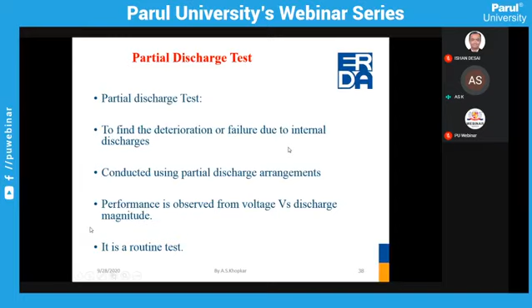So let's say we have produced 100 units. Out of that, we randomly select a sample, and then a few tests we conduct on those samples. If those samples pass, then the entire batch is passed for that particular test, and that's why it is called the acceptance test. So we have to accept the lot or not. The partial discharge test we conduct as a routine test, and it is to find out deterioration or failure due to internal discharges. This test has to be conducted.